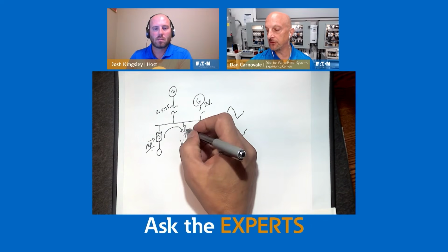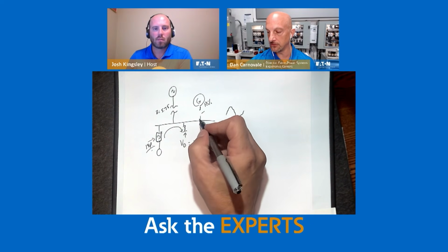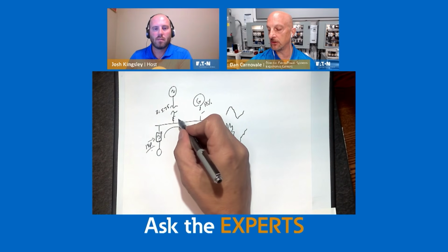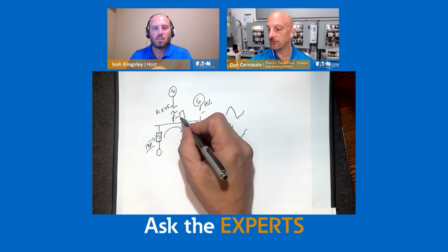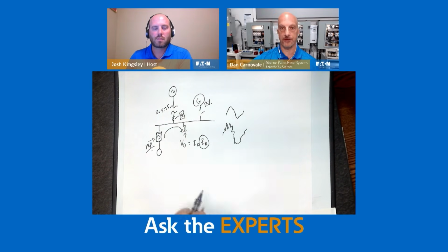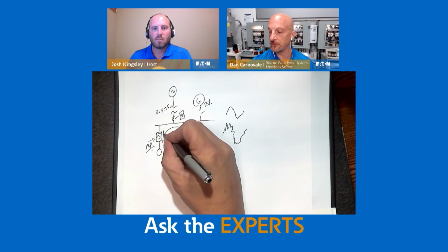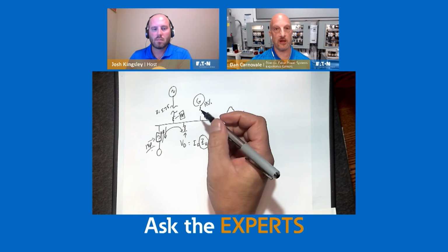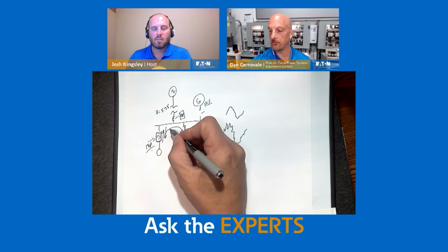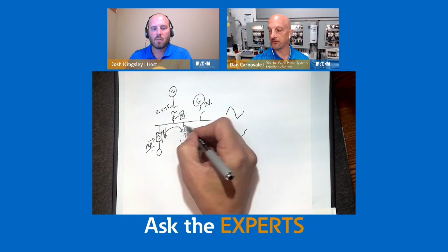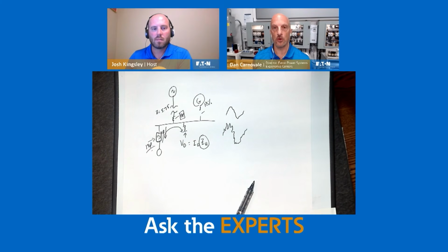Sometimes we do passive filters. Sometimes we do active filters. Active filters actually look at the current going through the system. And an active filter is like your cell phone having noise cancellation. Basically, it injects equal and opposite frequencies. So if the harmonic is coming out of the drive going this way, the active filter sends it that way. And again, since current flows in a loop, it goes out and back. And as far as the bus goes, the voltage goes back to normal. So yeah, lots of different things to think about, but it can be an individual drive solution or a system solution.